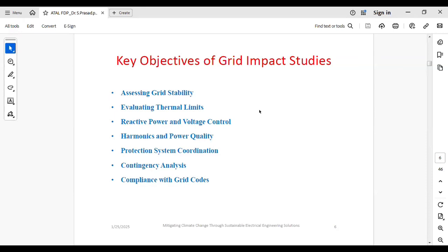So evaluating the thermal limits also. You have to check whether the transmission lines, the conductors, the cables, or the transformers are violating the thermal limits. We need to produce a report and submit it for approval. And reactive power is becoming one of the most important challenges, and voltage control at the grid bus. That means our interconnection point, which is called the point of interconnection, POI. At the POI, we need to check all these things.